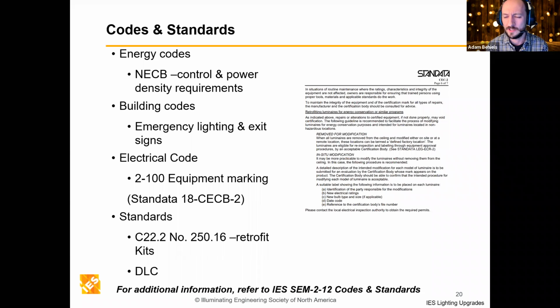One I'll point out that comes into play when you're doing retrofits is equipment marking - I've got a reference to a standard here. Effectively, when you're altering a luminaire, whether it's taken down for modification or modified on site, most times you'll need new equipment marking to identify whether lamps, ballasts or drivers have changed, or wiring's changed. So keep that in mind, that's an extra step you need - usually it's describing the retrofit to the certification body, they make up a new sticker, and the contractor puts that sticker on as they go through the retrofit.